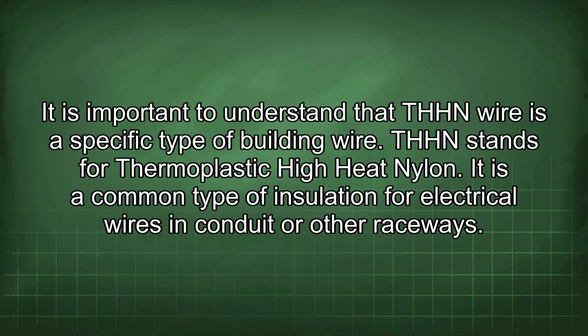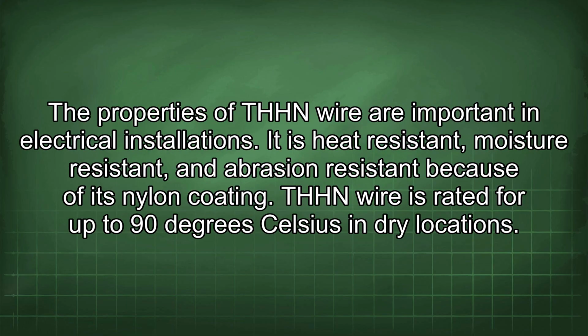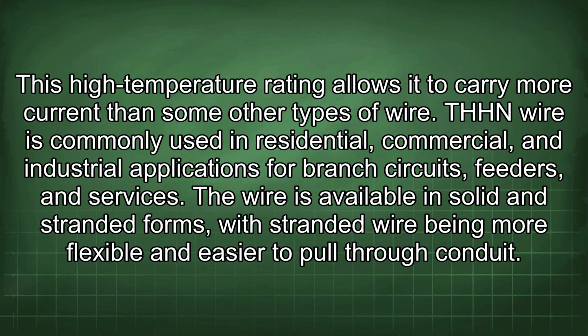It is important to understand that THHN wire is a specific type of building wire. THHN stands for thermoplastic high-heat nylon. It is a common type of insulation for electrical wires in conduit or other raceways. The properties of THHN wire are important in electrical installations. It is heat-resistant, moisture-resistant, and abrasion-resistant because of its nylon coating. THHN wire is rated for up to 90 degrees Celsius in dry locations. This high temperature rating allows it to carry more current than some other types of wire.